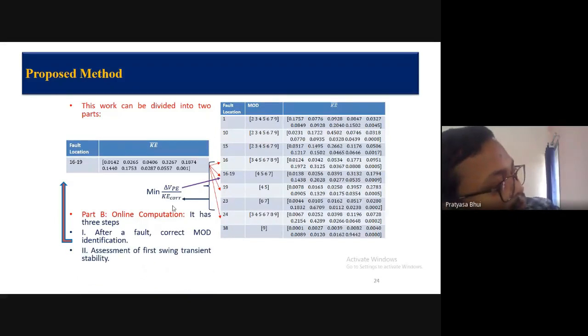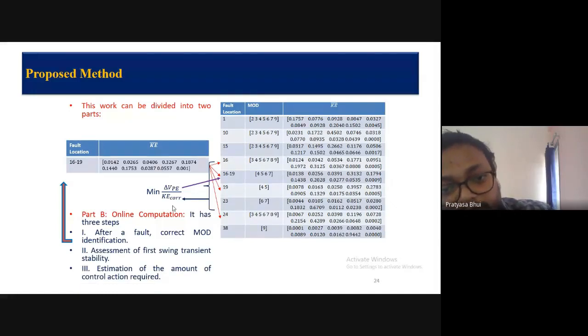Now, if you know that these four generators will become unstable, you can find theta, your unstable equilibrium point, as 180 minus the stable equilibrium points for the critical generators, and for the rest of the generators, it will be only the stable equilibrium point theta. So if you know the unstable equilibrium point, you can compute the delta V or the energy margin, and you can predict whether it will be stable or unstable. And based on that, you can decide the control action as well.